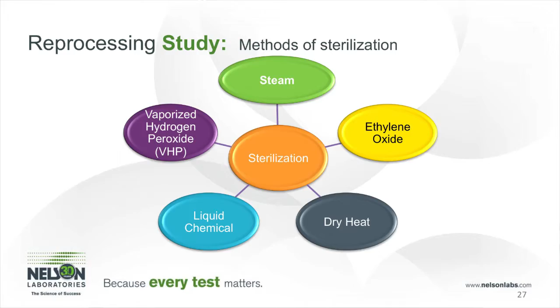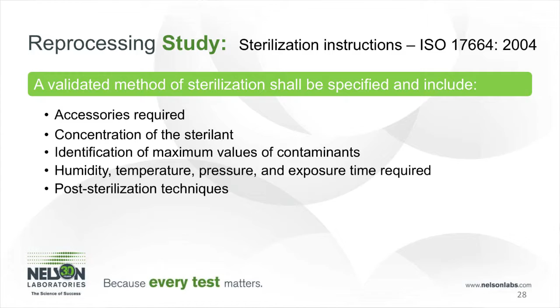ISO 17664 also specifies that a validated method of sterilization shall be performed. And we also need to include the specific accessories required for sterilization and the concentration of the sterilant. We need to specify the humidity, temperature, pressure, exposure time, and any specific post-sterilization steps. So if we perform ethylene oxide sterilization, we have to perform aeration along with that type of sterilization.